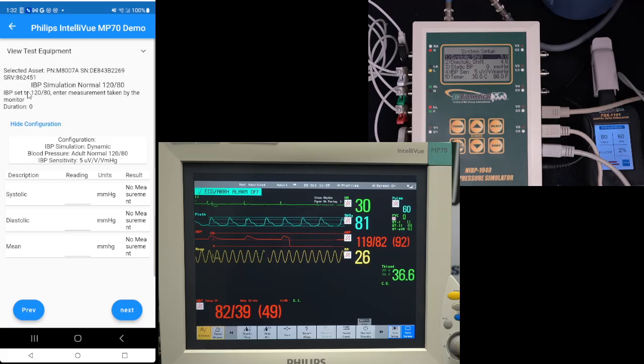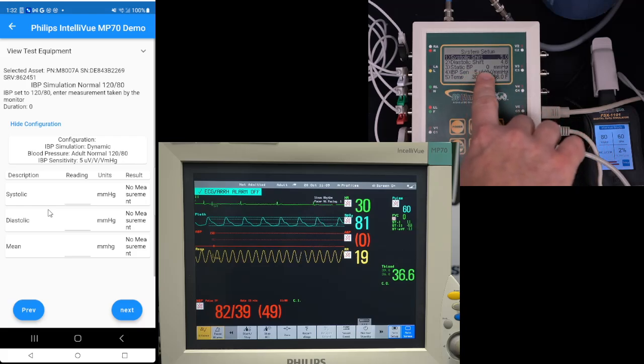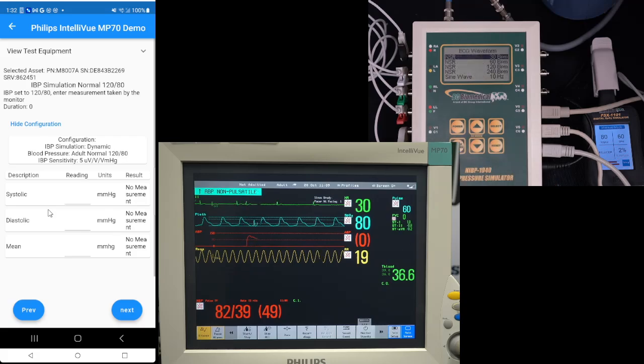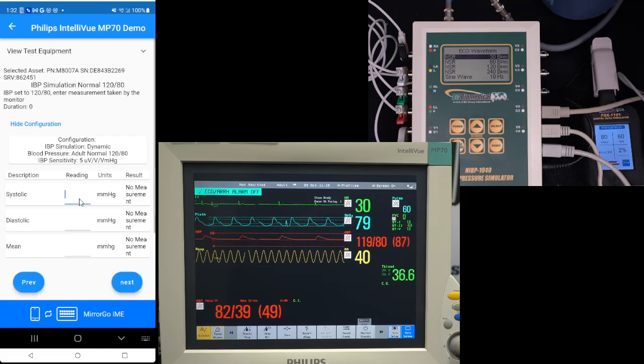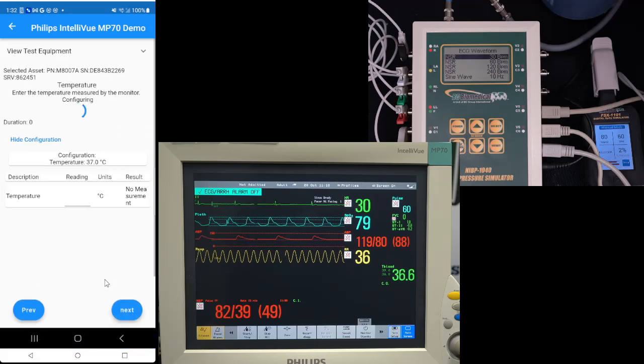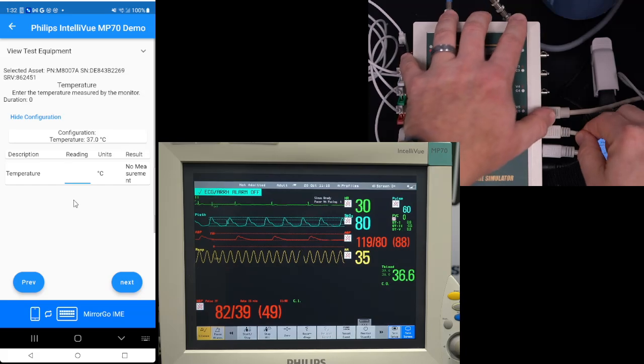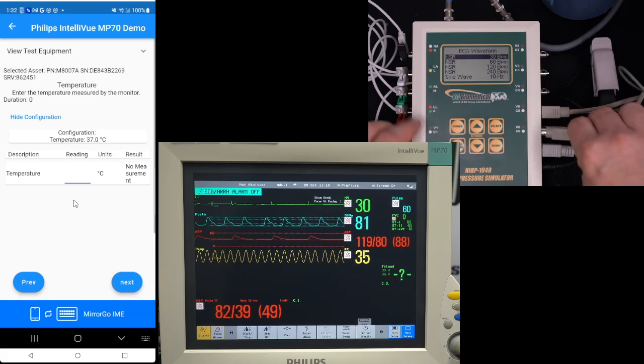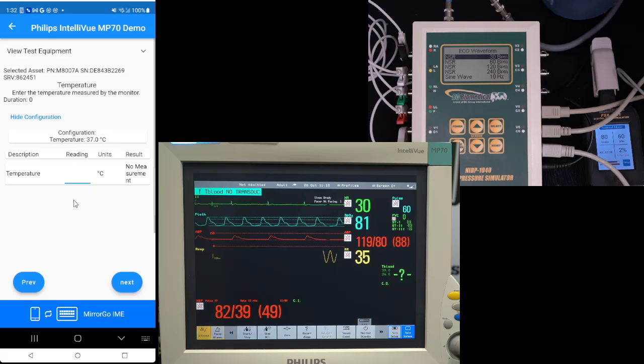And then we're going to do IBP, invasive blood pressure. It's in the setup menu, so I can do my 0. So I did my 0, and we'll go out of the setup menu. And we should get 120 over 80. 119 over 80. And 87. Now my temperature was connected to the cardiac output box. So I'll disconnect that, and I'll connect the cable for the temperature. 37 degrees. It's looking good.